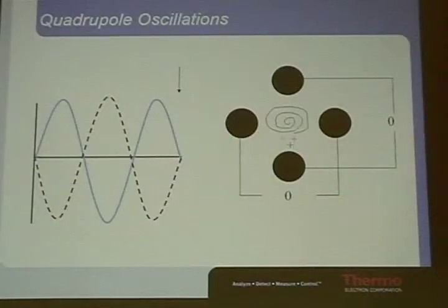So we use collisional cooling with background gas in an RF field to provide the circular motion with a negative DC offset to provide the forward motion, and we create a spiral that spirals in a very nice tight corkscrew and pops them through the next small hole.